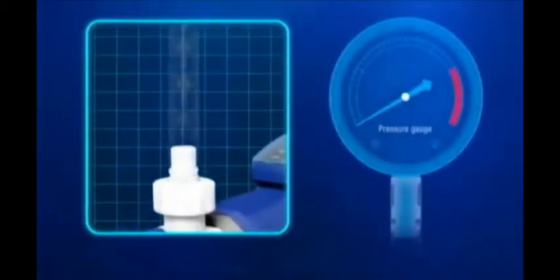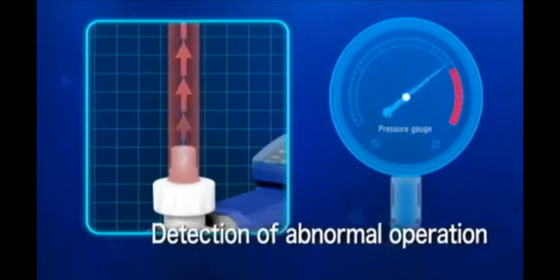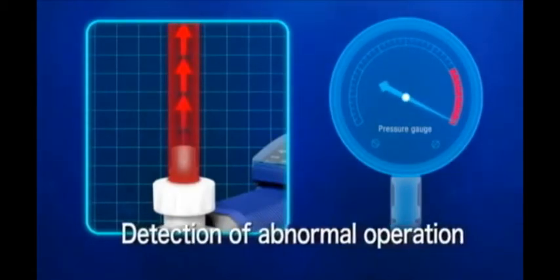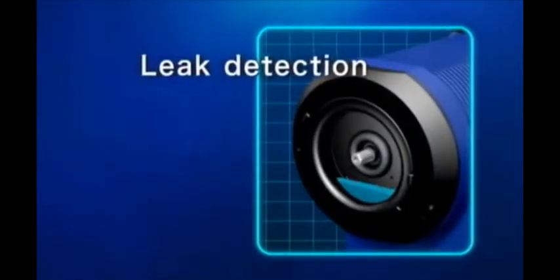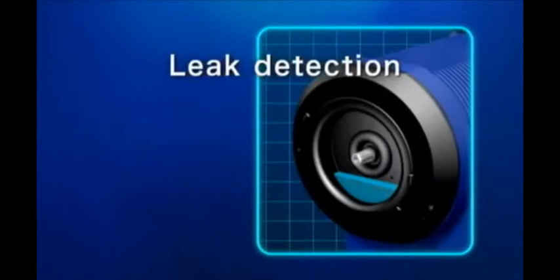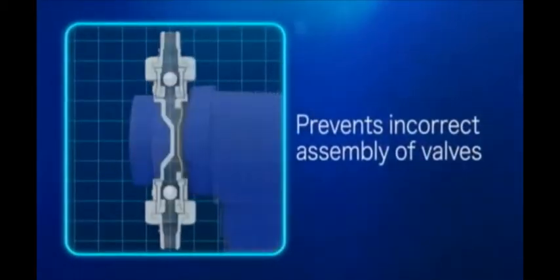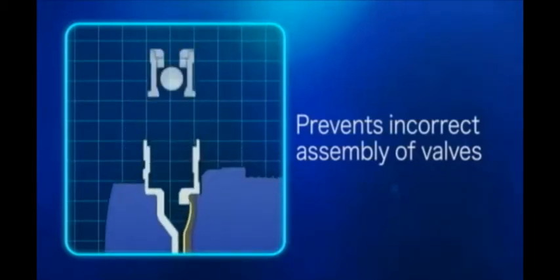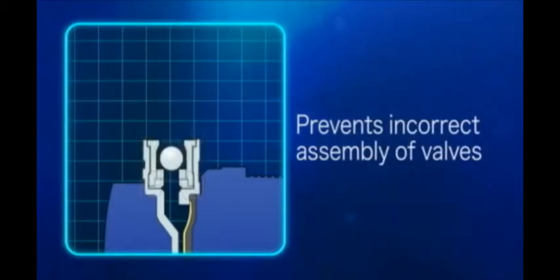The IX series pumps are equipped with features that ensure simple and safe operation. Abnormal operation is detected based on excessive load or based on a leak detection system that continuously monitors the diaphragm. Additionally, several other safety functions have been incorporated into the pump body, including a design that prevents the incorrect valve assembly that is common during maintenance operations.